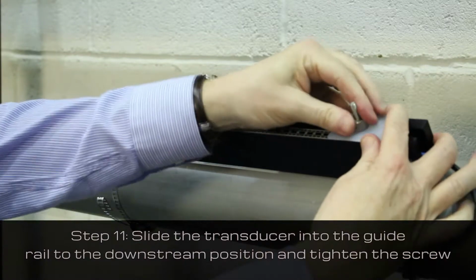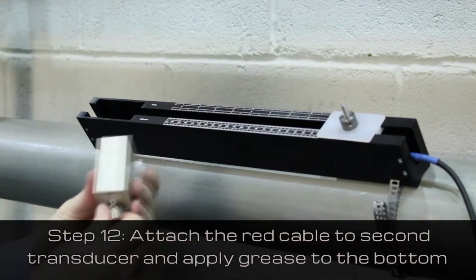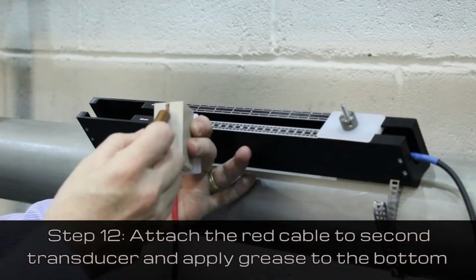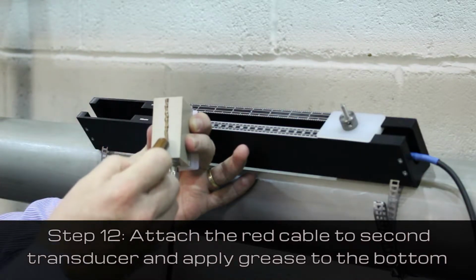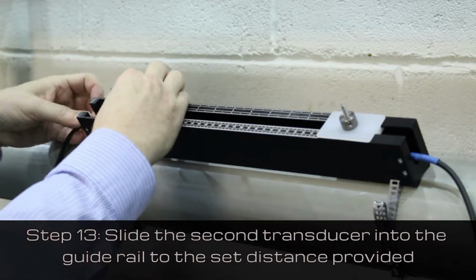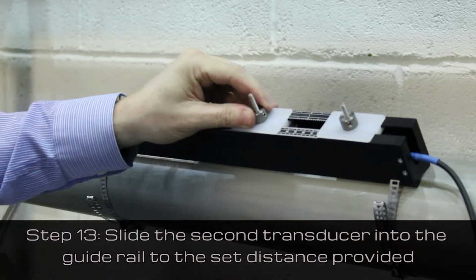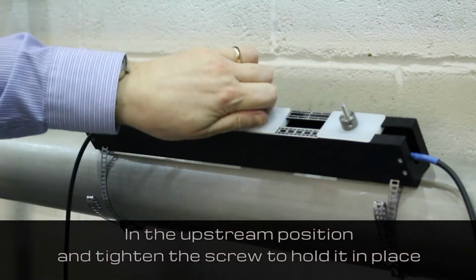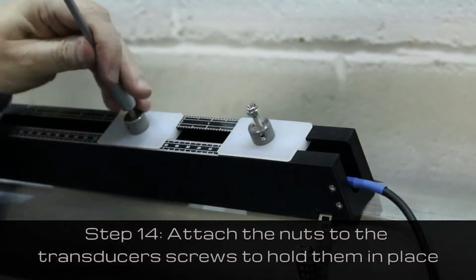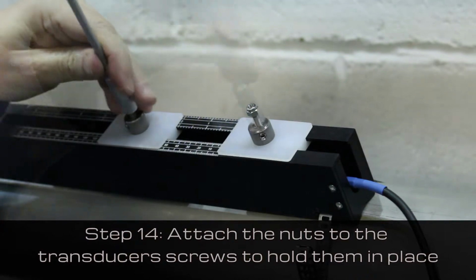And tighten the screw. Attach the red cable to the second transducer. Apply the grease and slide the transducer into the guide rail to the set distance provided by the flow meter in the upstream position and tighten the screw. Attach the nuts to the transducer screws to hold them in place.